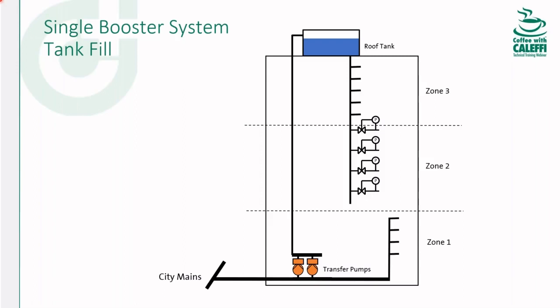And then for zone three and zone two, they're gravity fed from the tank that's on the roof. So no PRVs on zone three because the elevation head is low enough. But zone two, you're going to need PRVs just because of that static pressure. You have to knock it down.